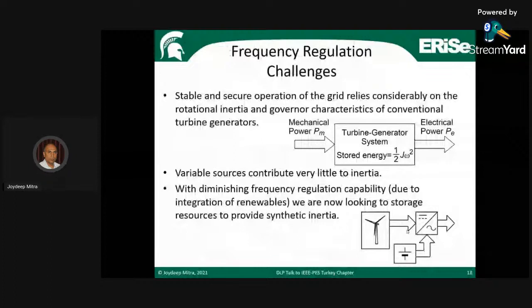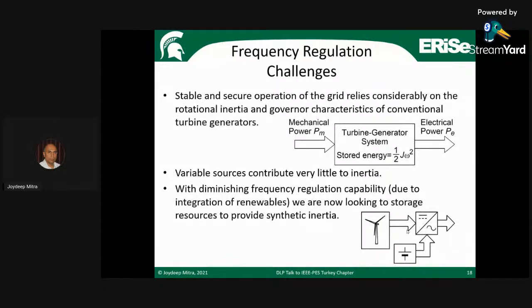I'm going to take a minute to explain the stability and frequency regulation issue. As you know, stable operation of the grid relies on the rotational inertia. I've given a graphic here, the top graphic, to explain this. What happens in a conventional generator is that there's this heavy turbine rotor mass that rotates at a fixed frequency of omega. In Turkey, I think it's 50 hertz, right?